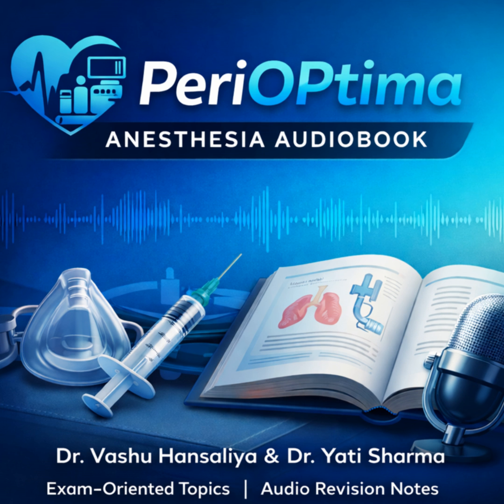Autoclave: high temperature, 121 degrees or more. ETO: low temperature, 37 to 55 degrees. Autoclave: short cycle time measured in minutes. ETO: long cycle time measured in hours, plus aeration. Autoclave is for heat-stable items like metal and linen. ETO is for heat-labile items like plastics and delicate electronics.